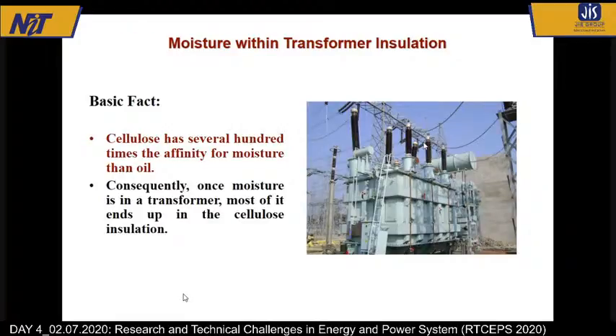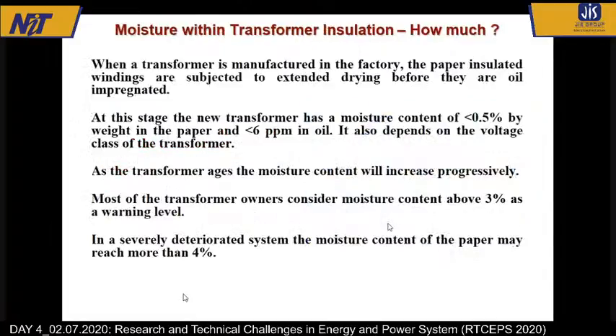The whole situation is that moisture is generated, then it is attracted by the paper, so it goes to the paper and damages the paper. And then further moisture will be generated. So this is the entire process by which this very expensive equipment slowly goes towards fault. As I was telling you about how much the moisture content will be, as in the second paragraph you can see, at the time of installation, generally it is less than 0.5% by weight in the paper and less than 6 parts per million in oil. This is the typically expected value. But as the transformer is used, the moisture content can reach 3%, then we say this is the warning level. And at the bottom, you can see that if it goes around 4%, then the condition is very poor.